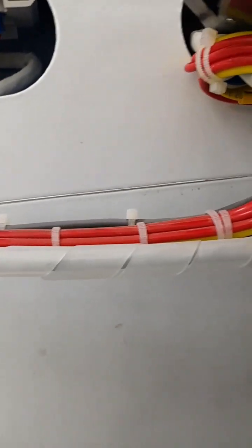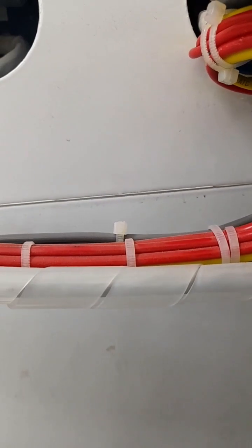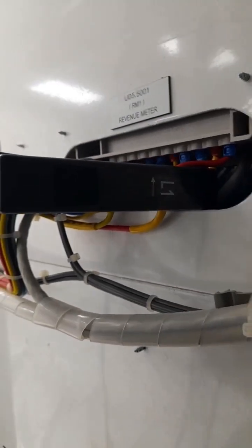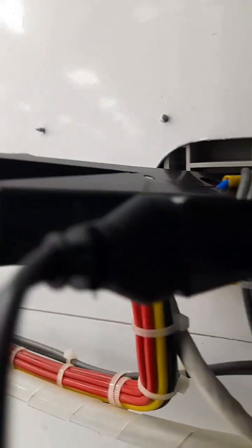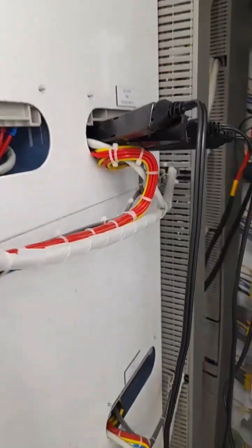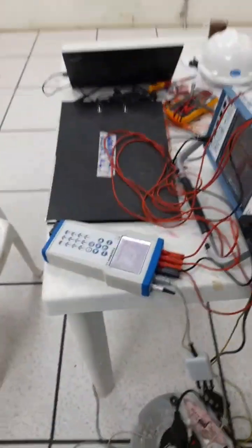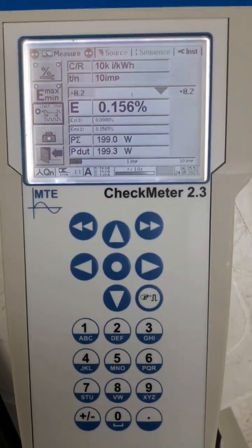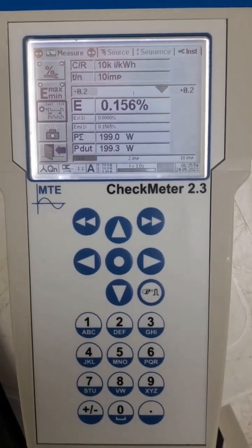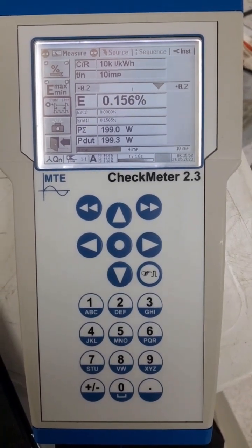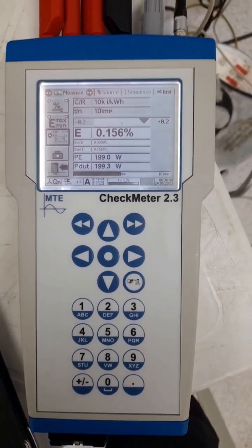Again I'll make it properly. Okay, now I fixed it. It should be like this. This is very important. It will make a huge difference in your accuracy if you install wrongly. See, now again the power value is 199 and P DUT is 199.3. The error is under the limit.